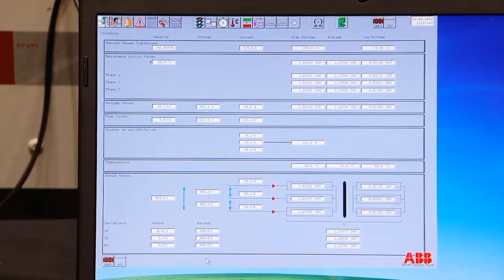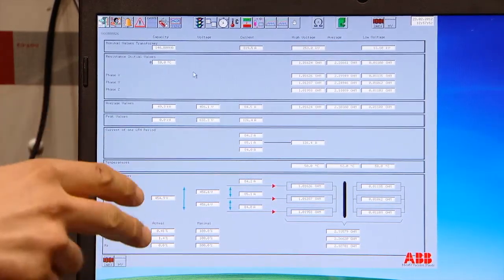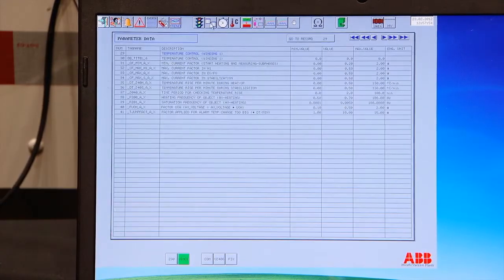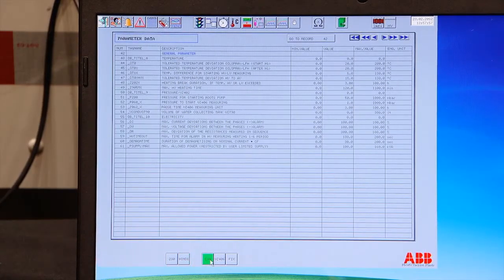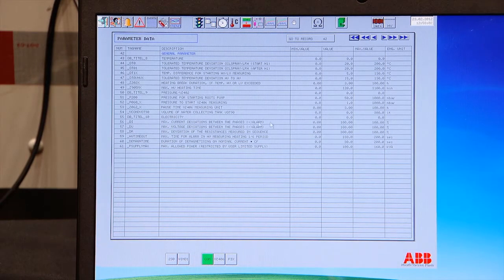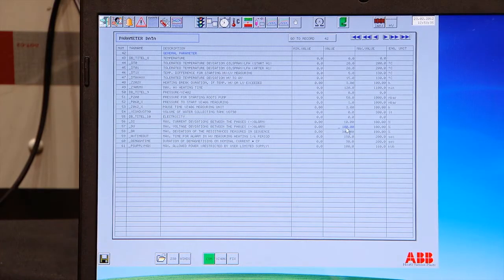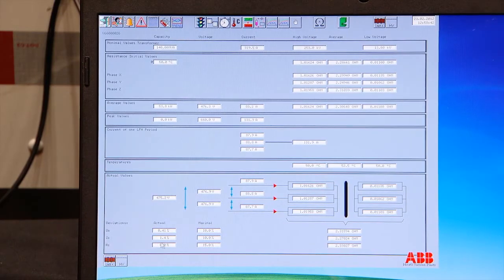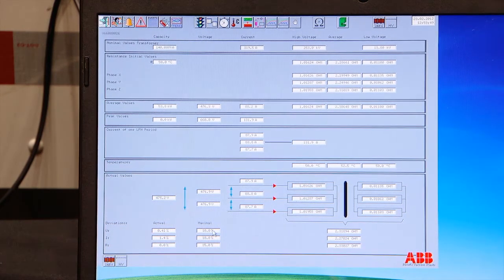We can manually change that. It's on the common page of the parameters, maximum current deviation. This is when you will have an alarm. You put it to 10, 10, 15. Going back to our resistance page: when the deviation in voltage goes over 10%, the converter will stop and you will have an alarm.